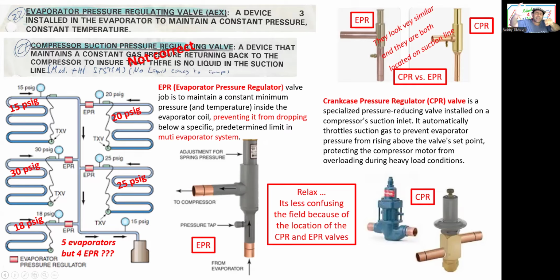Thermostat, I can set the thermostat at 0 degrees on the air conditioner. We'll never get to zero because the EPR, the evaporator pressure regulator, will keep pressure above a certain temperature. This is important in refrigeration when you have a supermarket with a multi-evaporator system: one for produce at 50 degrees, one for eggs at 45, one for beer and soda at 35, one for meat at 25, and one for regular food at 38. Different products need different temperatures, but they all share one compressor. So that's why we have EPR valves.